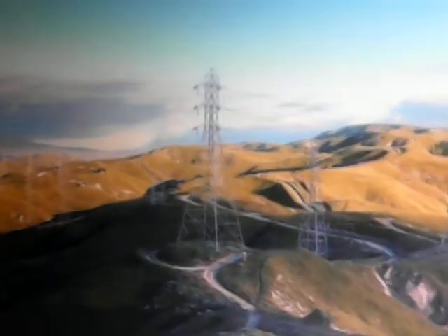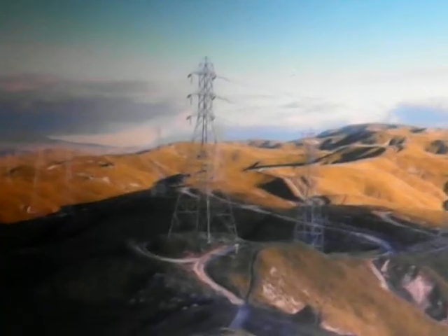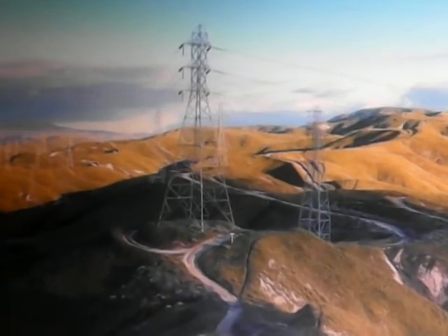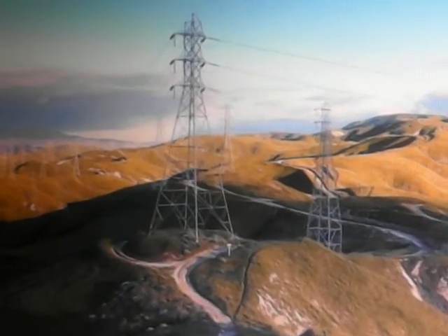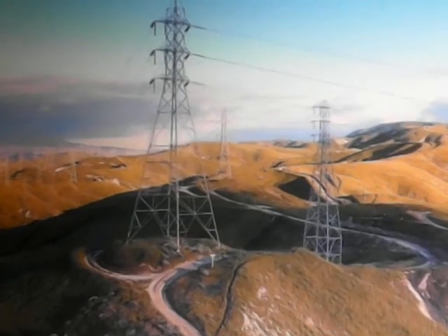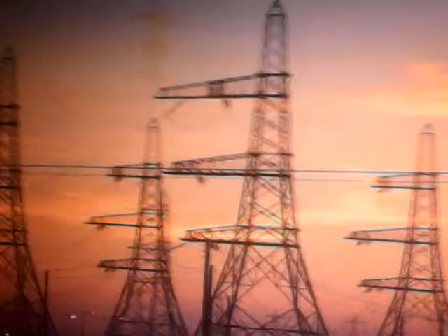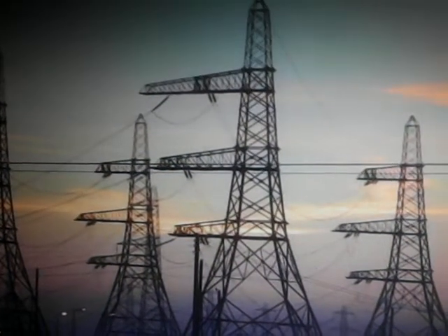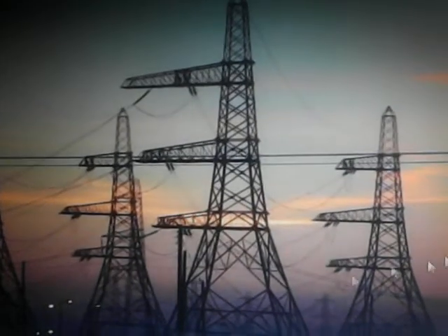Saturated transformers are the root cause of most grid malfunctions during magnetic storms. However, in 1989, the knock-on effect of these waveform distortions is what caused the majority of the damage, as electromechanical protective relays tripped and cut off sections of the grid.